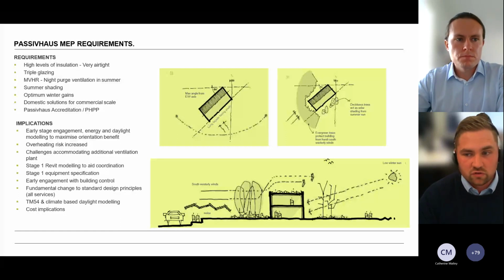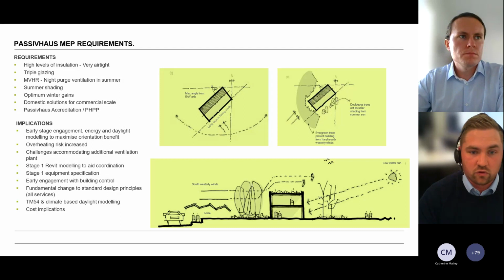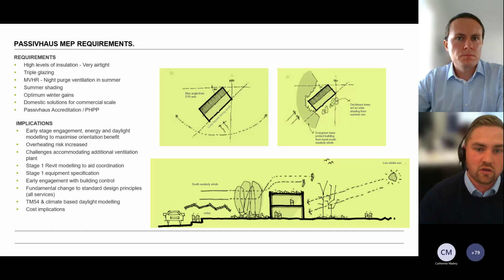We're looking at MVHR units - there are multiple in the project serving all the floors, and every single room in the building is mechanically ventilated, which is another requirement for Passive House. Because the MVHR units are certified, we're getting up to 92% efficiency on that unit, using a counterflow plate heat exchanger to get the best out of it. As design engineers, we need to make sure our specification achieves that to get Passive House certification at the end.